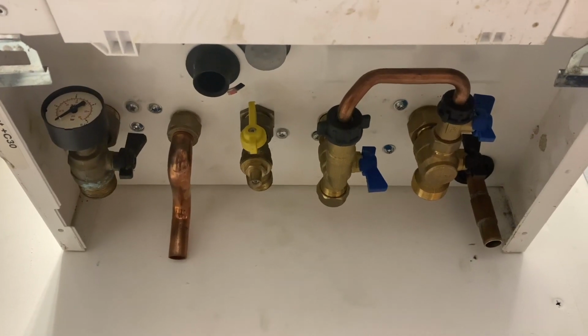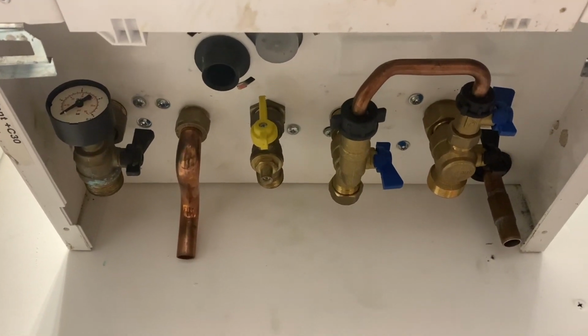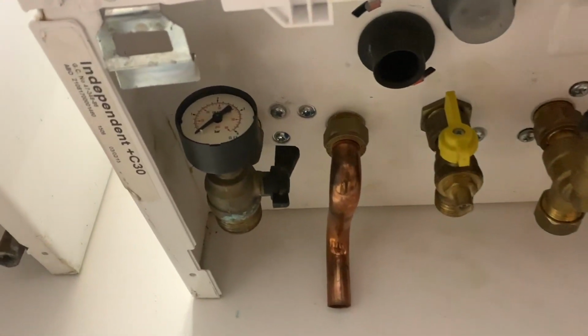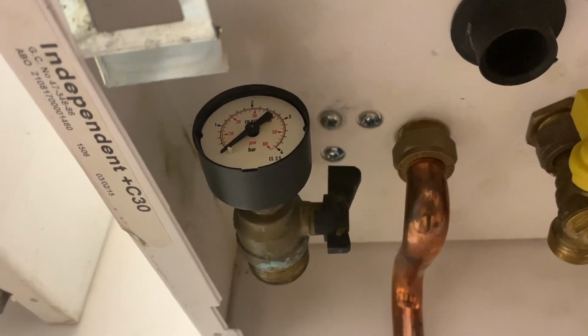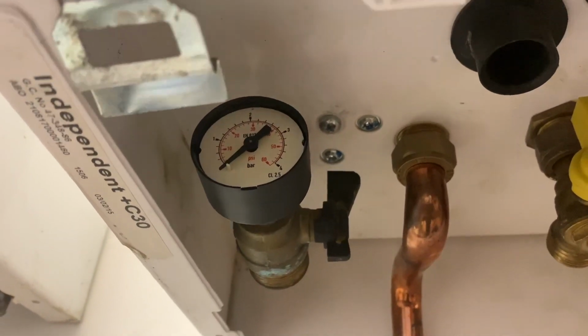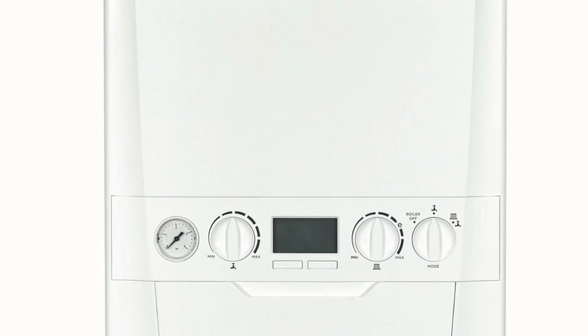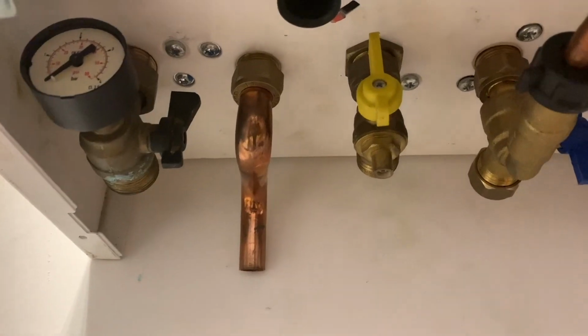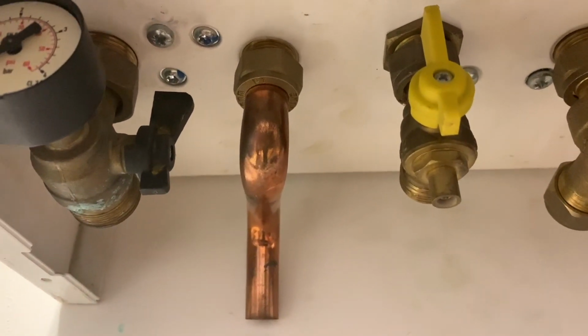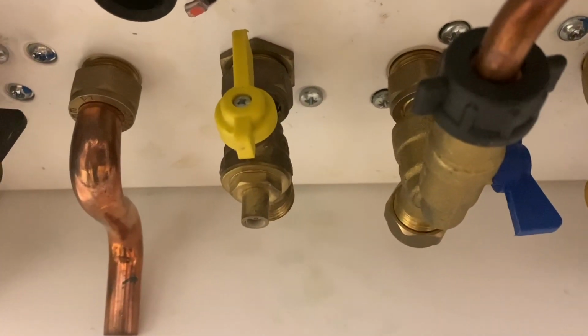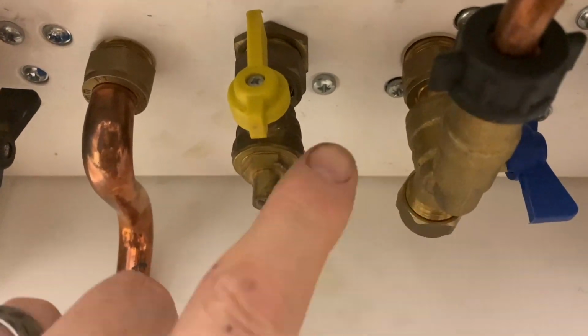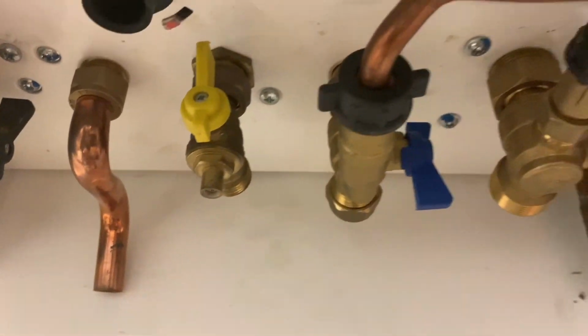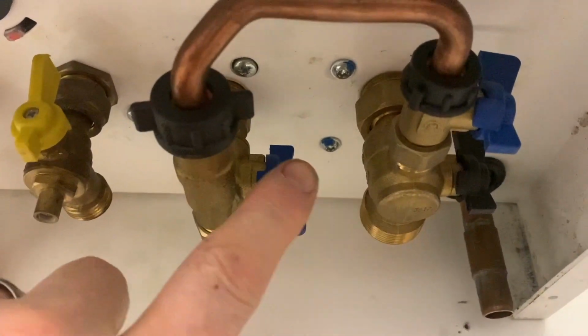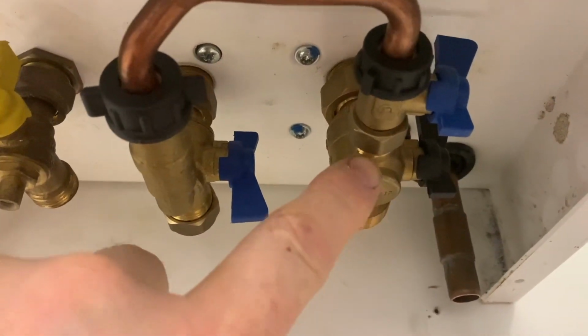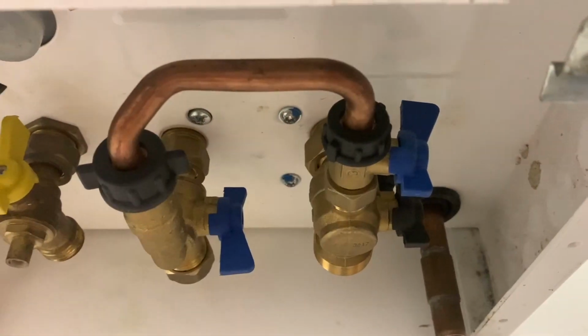Now, as always, and inside the boiler casing, let's finish off underneath the boiler. So to the left, you can see this is our flow outlet, and you can see there is a pressure gauge. Now on the brand new models, this pressure gauge has been moved to the front casing of the boiler so you can see it easily. Next, we've got the hot water outlet. Then we've got our gas with our inlet test nipple. Next one we've got is our cold water and our return with our integral filling loop.